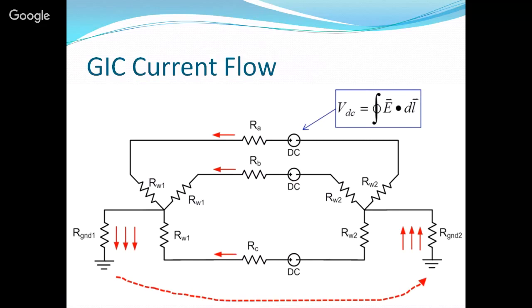If it was just that current flowing through, you wouldn't have a problem. But you're also trying to meet demand. So half the AC cycle, you're saturating your transformer, the other half you're not. And if you've ever put DC into a transformer, you know it causes bad things.